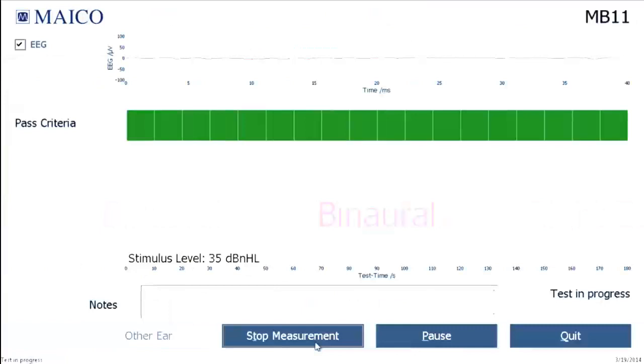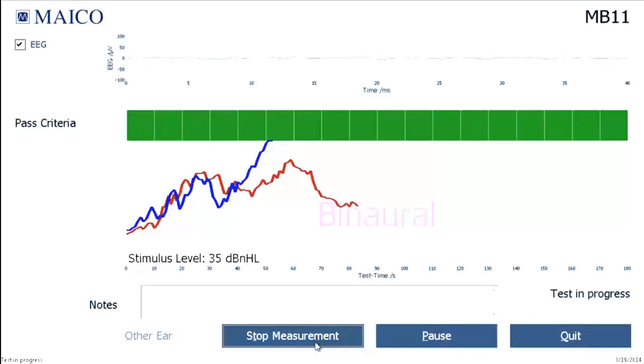When you perform a binaural test using the Classic hardware, a line will display for each ear on the same graph. It's common for one ear to achieve a pass result before the other ear. The screening will continue until both ears have achieved a pass result. After 180 seconds of good ABR data samples have been collected without the line ascending and crossing into the green area for both ears, the screening will stop automatically with a refer result.